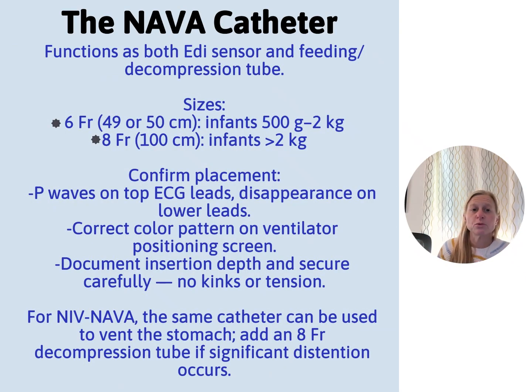As far as the catheter goes, remember the NAVA catheter functions as both the EDI sensor and a feeding or decompression tube. It comes in a 6 French and an 8 French. There are 2 lengths in the 6 French, which I know you're probably wondering about, why is there a 49 and a 50? That's the location of the electrodes. So it is important. There is an 8 French, and the 8 French is longer, so it's going to tell you where the electrodes are as well. When you have good placement, you really are looking at the ventilator. I'll show you on the next slide, but you want the P waves on top to look like EKG leads and then have the disappearance on the lower leads. You want the correct color pattern, and you want to document the insertion depth.